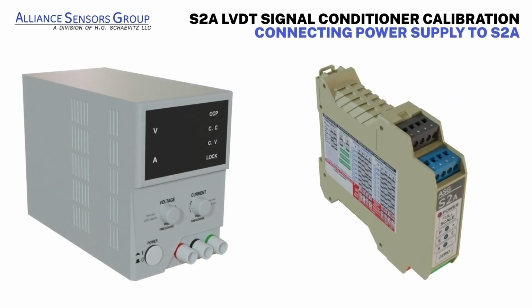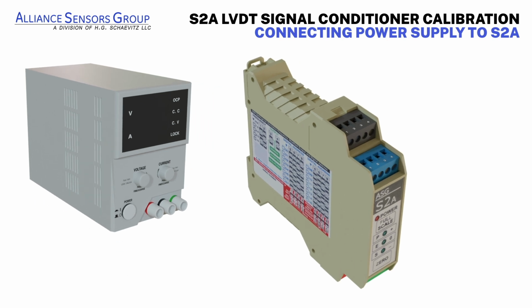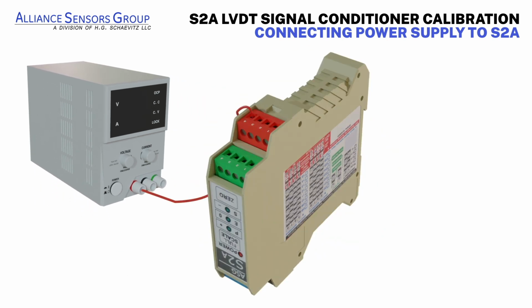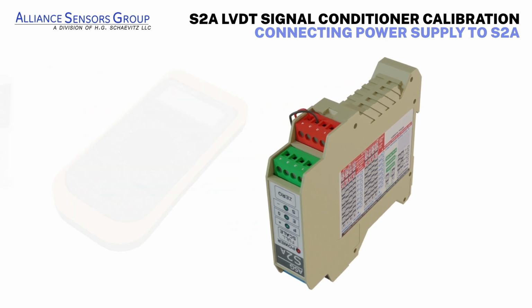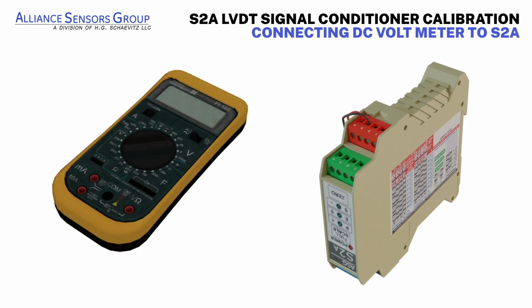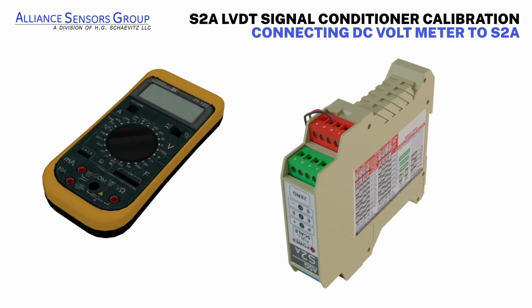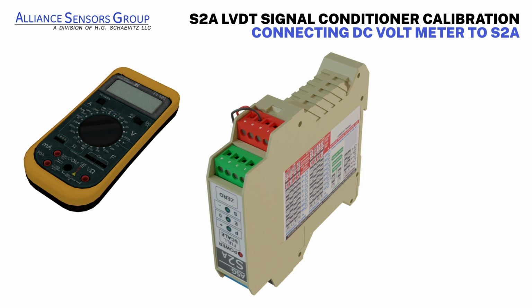After any internal configurations are complete, begin by connecting the 24-volt power supply. Connect the positive side of the power supply to terminal 4 of the red J4 terminal plug and the negative side of the power supply to terminal 3. Next, connect the digital voltmeter, which will measure the output from the S2A. Connect the positive probe of the voltmeter to terminal 4 of the J3 green terminal plug and the negative probe of the voltmeter to terminal 3 of J3.